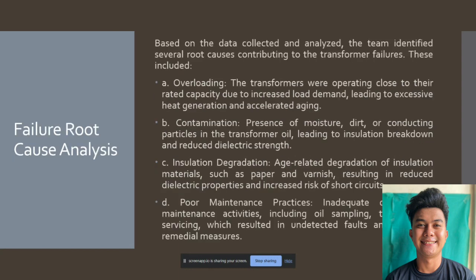Next is the failure root cause analysis. Based on the data collected and analyzed, the team identified several root causes contributing to the transformer failures. This includes, first, overloading. The transformers were operating close to their rated capacity due to increased load demand, leading to excessive heat generation and accelerating aging. Second is contamination. Presence of moisture, dirt, and conducting particles in the transformer oil, leading to insulation breakdown and reduced dielectric strength.